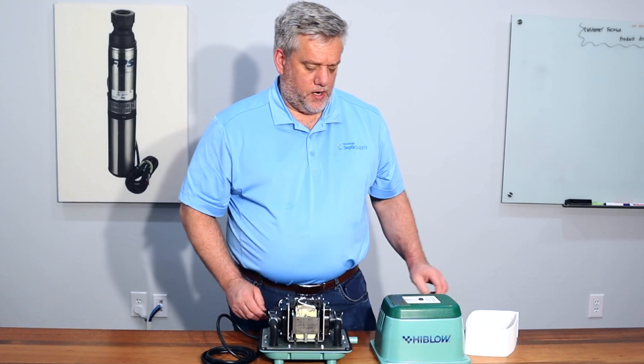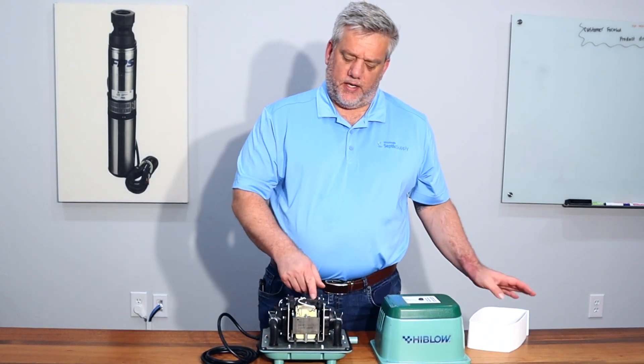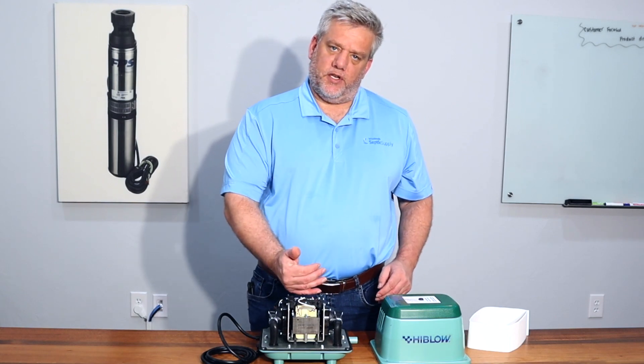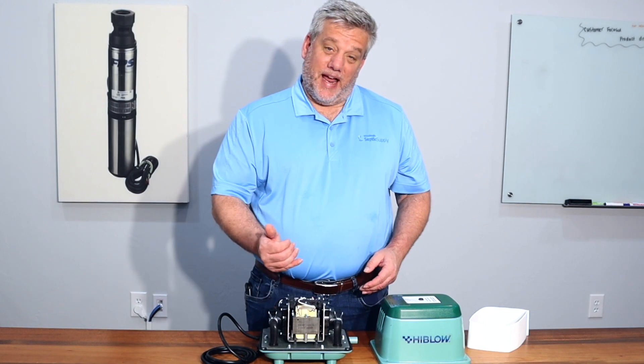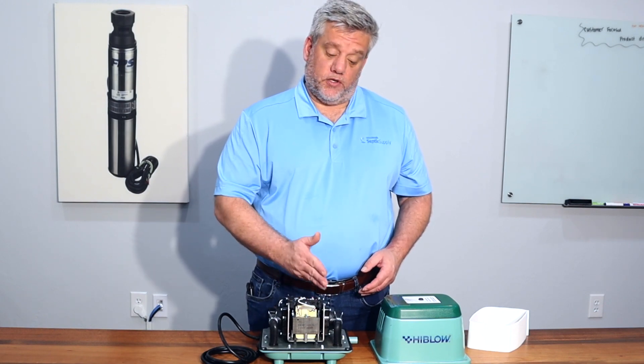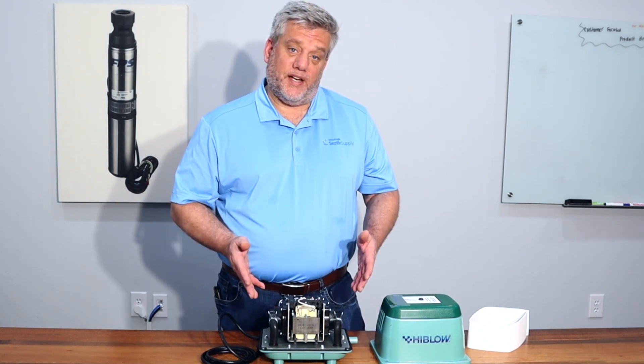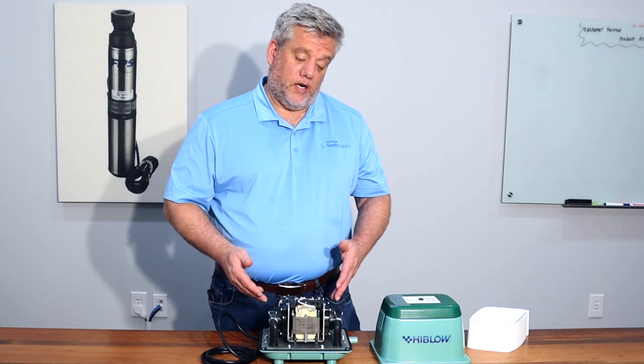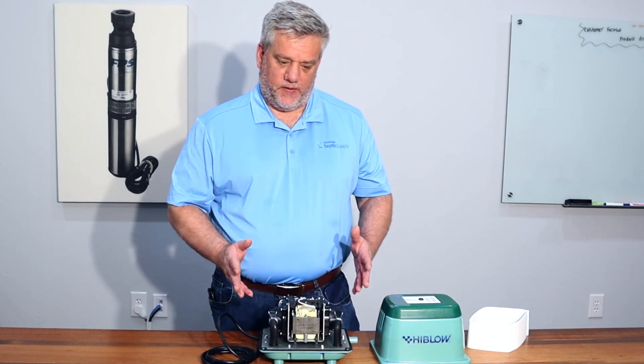The Hiblow 80 also has features such as the safety screw brakes, so the unit doesn't damage itself when the diaphragms do blow out. 99% of the time if the unit stops and this is broken, one of the diaphragms is damaged and you need to rebuild it. Another good thing is you can rebuild these about two or three times before you need to buy a new one, and they run right back to factory specifications.